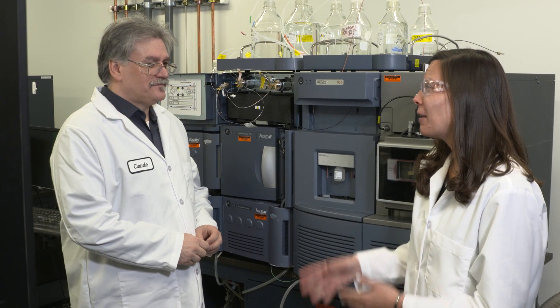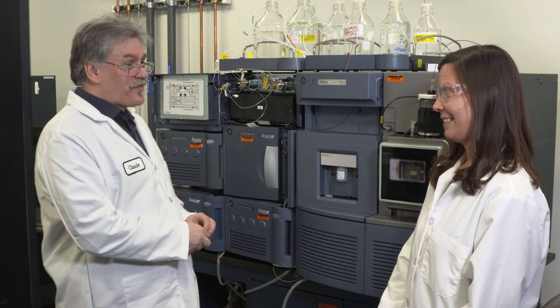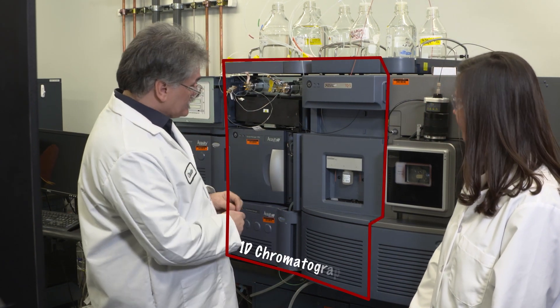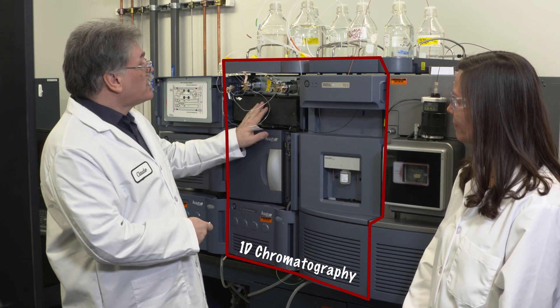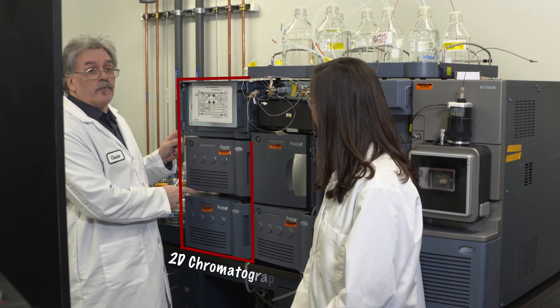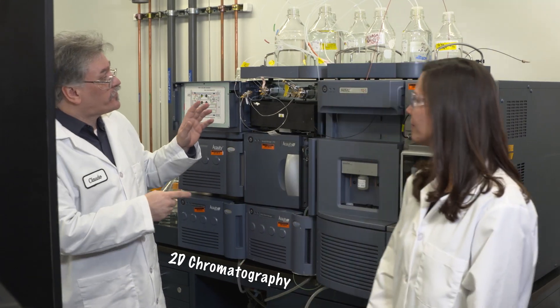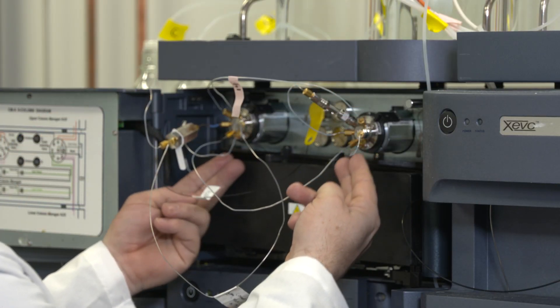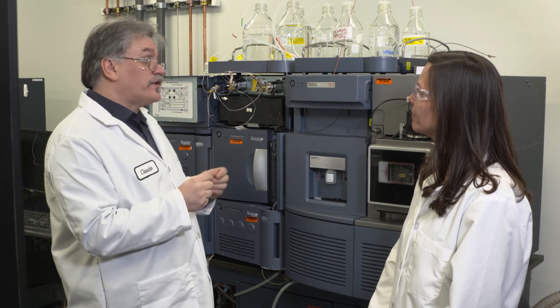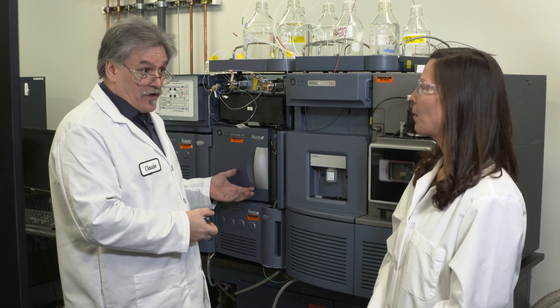That data is pretty convincing, but I have to tell you I've heard that multi-dimensional chromatography is pretty hard. It is a myth, and a myth that's actually easy to bust. Let me show you around. A 1D chromatography system would look something like this, constituted with a pump, autosampler, column manager, and a mass spectrometer detector. In multi-dimensional chromatography we scale back and add two extra pumps — or any pumps you want — to create the circuitry we have over here. We have our extraction columns, trap columns, and we can add more resolution columns to create a specific configuration for a specific purpose. But why would you want to add pumps to an already complex system? Workflow — your workflow will benefit big time. In this sense we can inject large volume injections for that purpose. But the proof is in the data — let's take a look at the whiteboard.